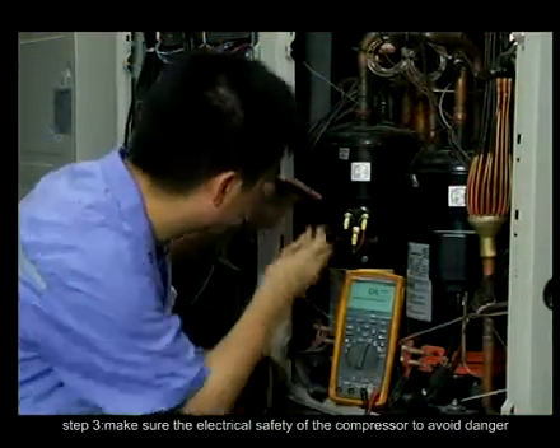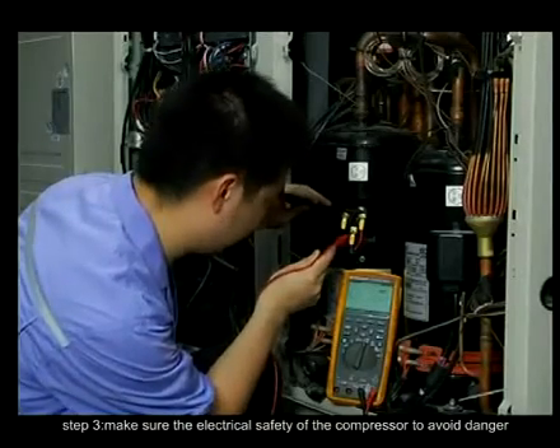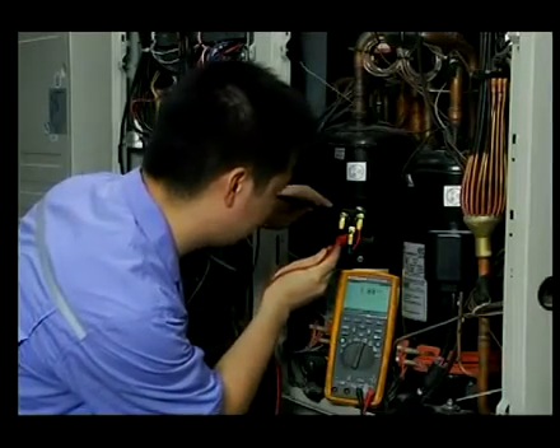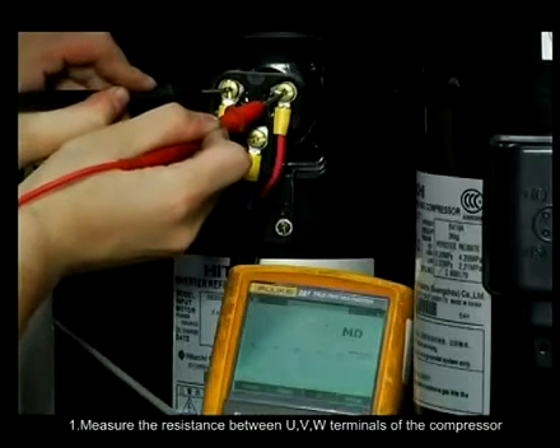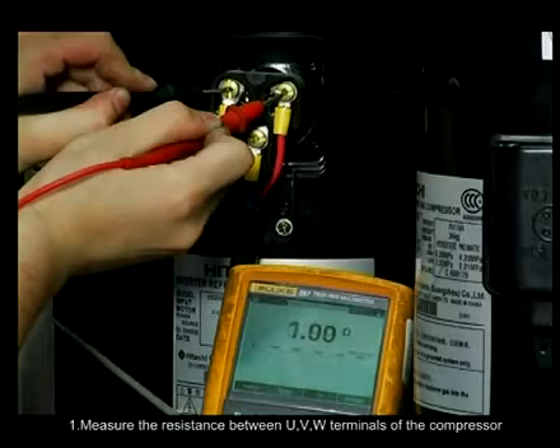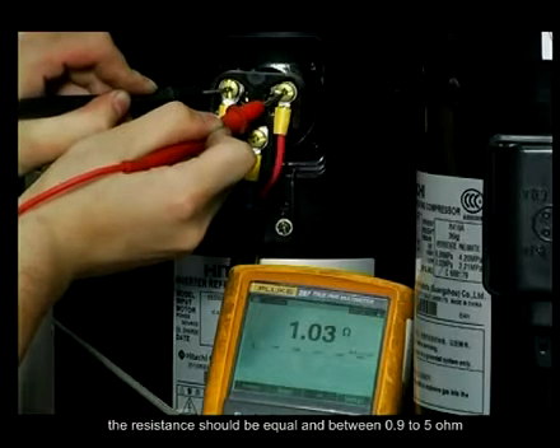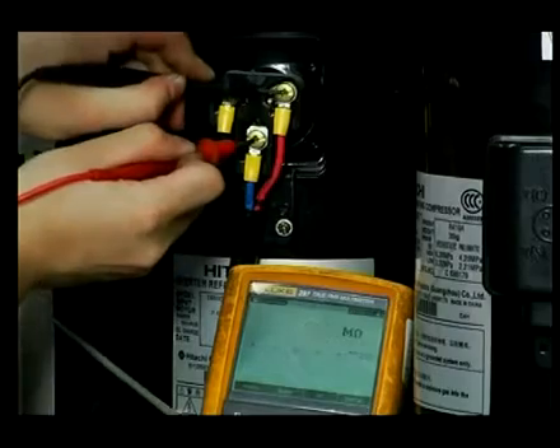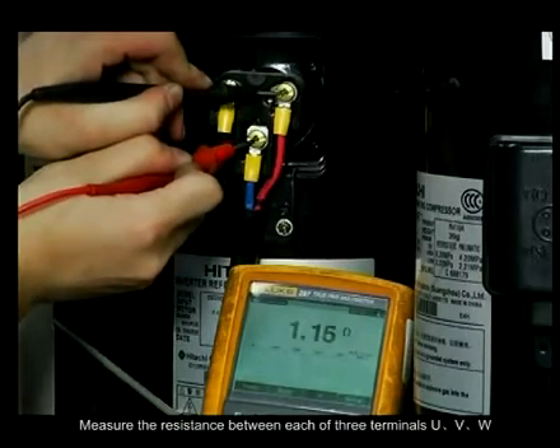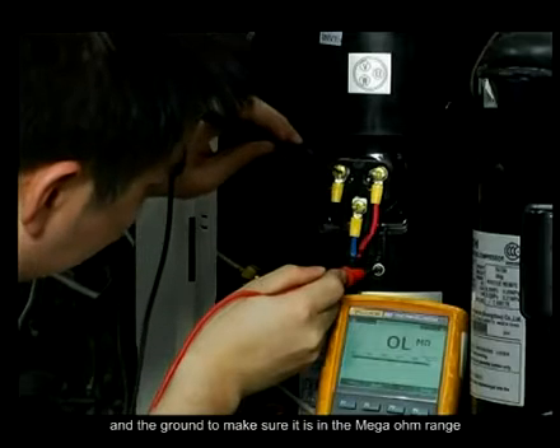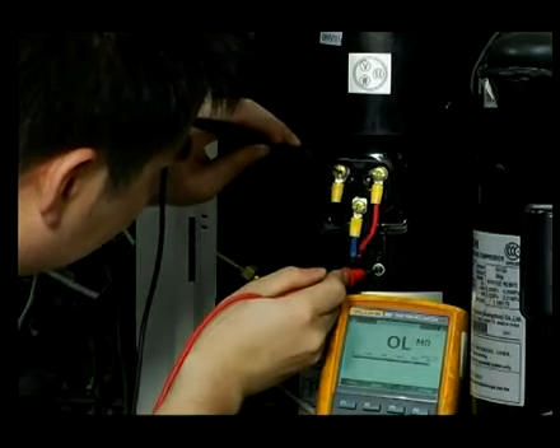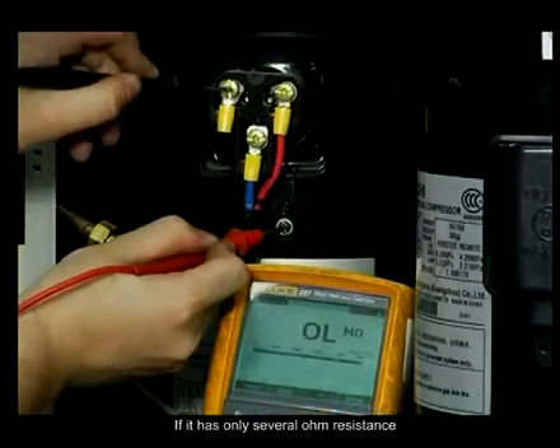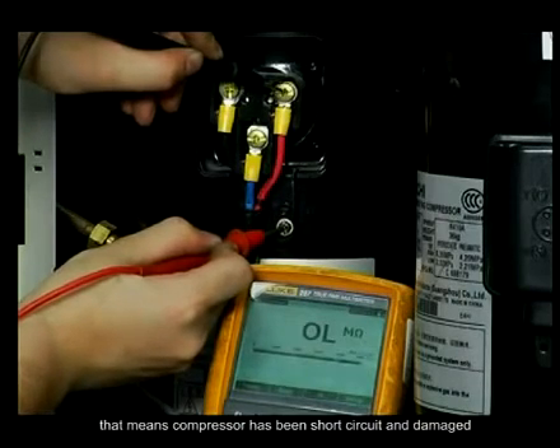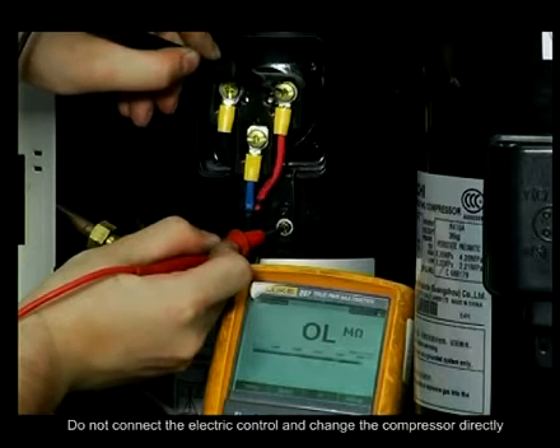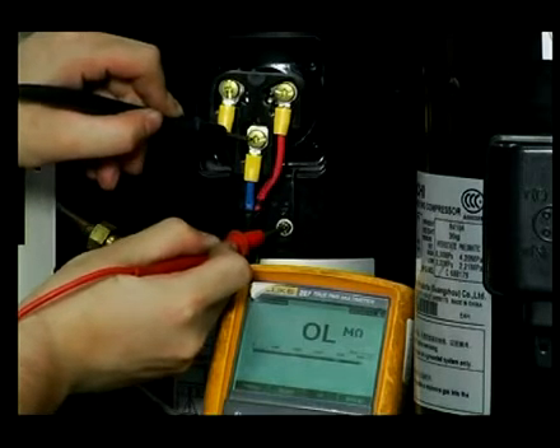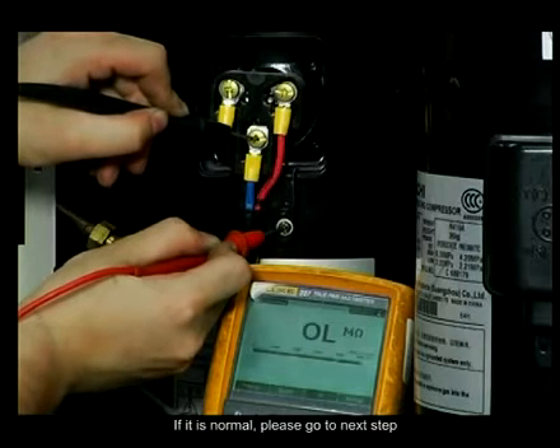Step 3. Make sure of the electric safety of the compressor to avoid danger. 1. Measure the resistance between the U, V, W terminals of the compressor. The resistance should be between 0.9 and 5 ohm. Measure the resistance between each of the three terminals, U, V, W, and the ground to make sure it is in the megaohm range. If it has only several ohms of resistance, that means the compressor has been short circuited and damaged. Do not connect the electrical control and change the compressor directly. If it is normal, please go to the next step.